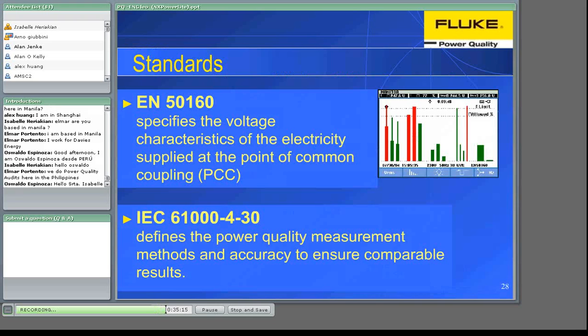The second one, more recent, is 61000-4-30 and is applied to the instrumentation and defines the power quality measurement methods or procedure and the accuracy to ensure comparable results between different measuring instruments. This standard 61000-4-30 classifies devices in class A and class B. Class A devices are more accurate, and usually they have to be applied in case of dispute between who is selling and who is buying the electricity.